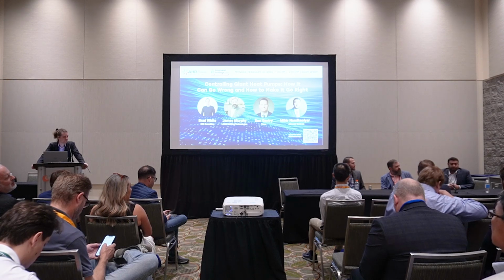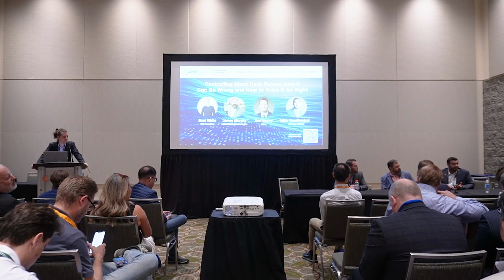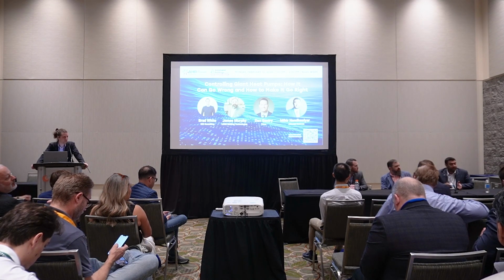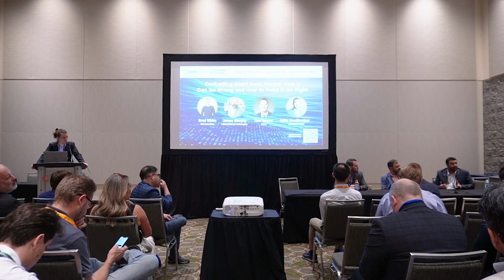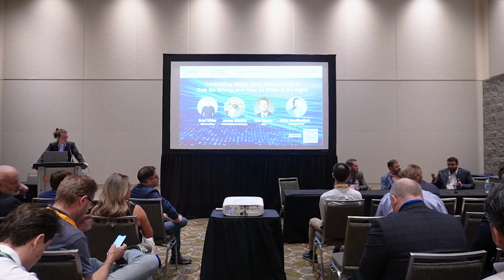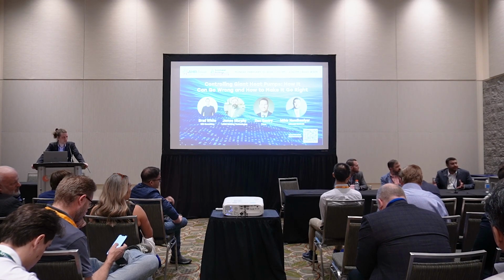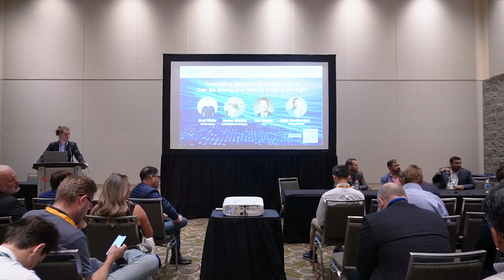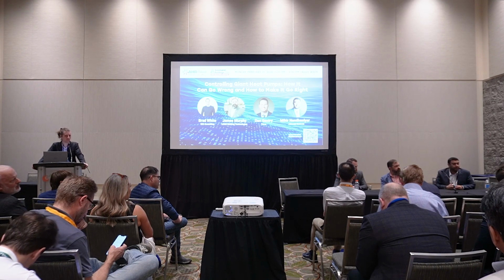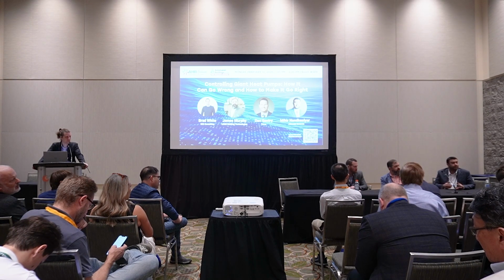If we're centering the conversation around air source heat pumps, they absolutely need a lot of volume for a couple of reasons. One, the modularity of it, right? You're talking about 30-ton or 40-ton or 50-ton blocks that build up your capacity. The other thing is, you've got a concern about defrost. In the 20 to 40 degree Fahrenheit ambient range, a large percentage, 30% of your units may not be heating, or refrigerant circuits may not be heating at that moment. Thermal storage certainly helps with preventing coils from suddenly seeing a huge drop in set point or supply water temperature, because you've got some of that buffer built into the system when that number of units go out of heating and into defrost and back.